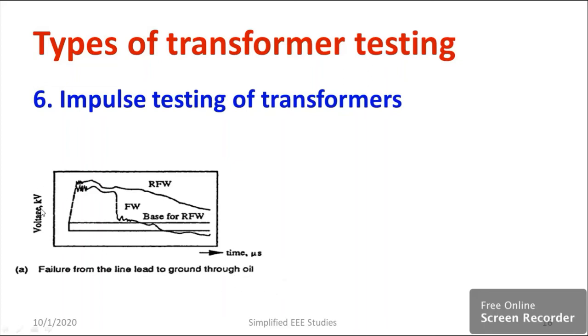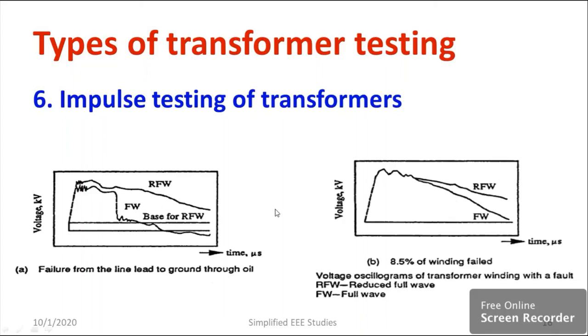That is a failure — so we are looking at output voltage versus time. If you see these kinds of waveforms, there is a problem in the transformer oil — a failure from line lead to ground through the oil. Similarly, consider another example: FW stands for full wave impulse, and RFW stands for reduced full wave. If you get these kinds of waveforms, it indicates that approximately 8.5% of the winding insulation has failed.